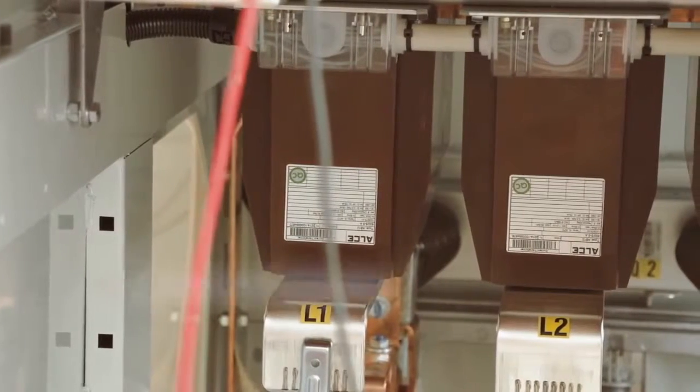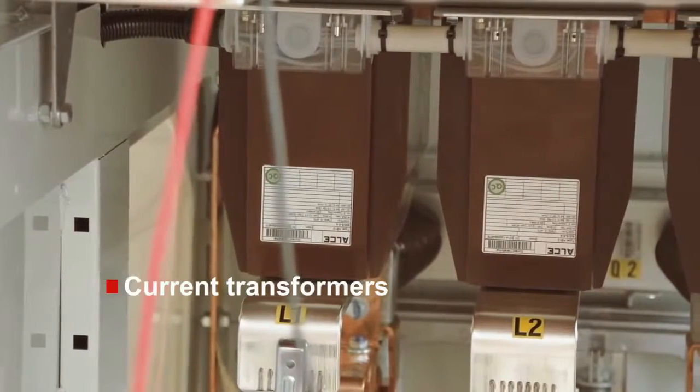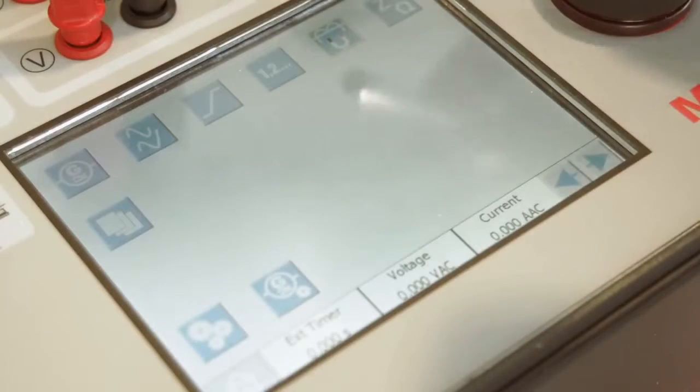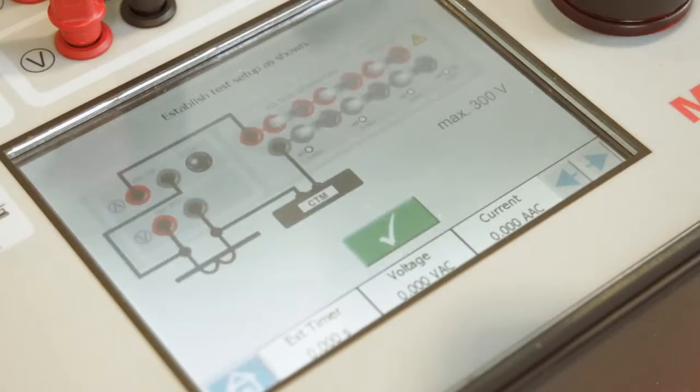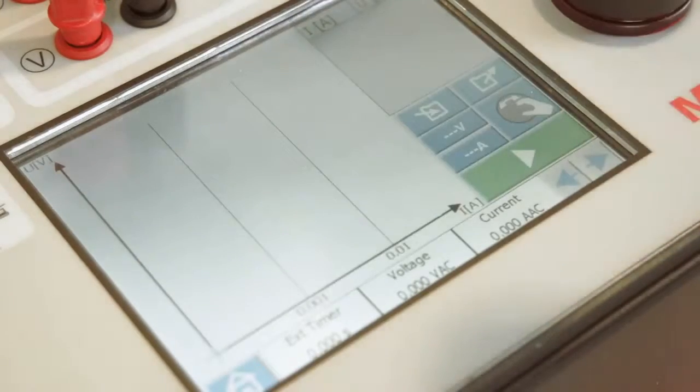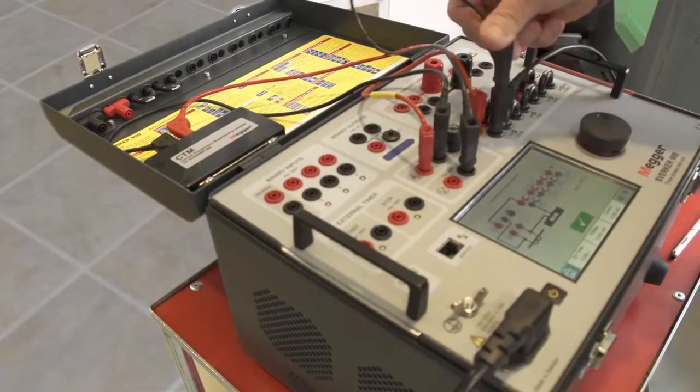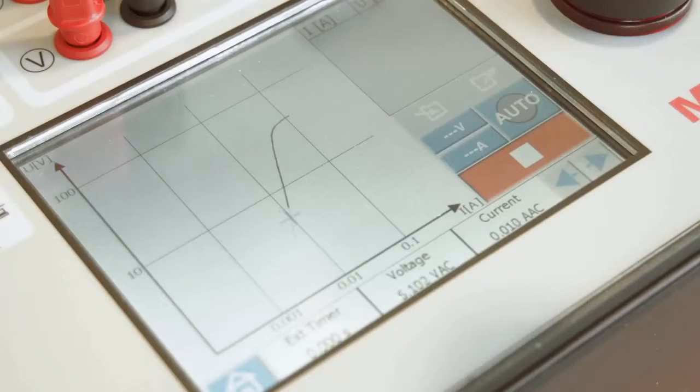One of the most common tests of current transformers is the determination of the knee point value. This can be easily done with the built-in instruments of the Sverker 900. The user is guided as to how to connect and can perform the test in a fully automatic mode as well as under manual control.